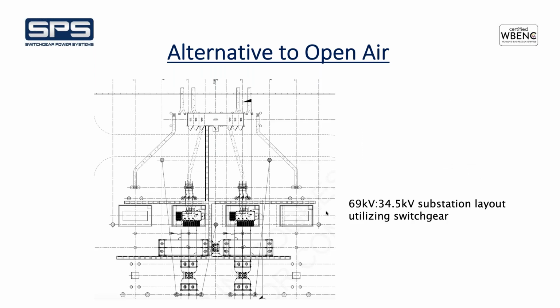So this is a top view of that substation. It's a 69 kV primary, and you can see that they come off of the transformer. There is the utility metering, and then underground feeding the switchgear. Some of our customers prefer to keep everything overhead, in which case we would supply roof bushings to connect the same way you would connect to an outdoor station breaker. So for contractors who are used to coming off of the transformer right into roof bushings, into circuit breakers, we can provide that same functionality with our switchgear.